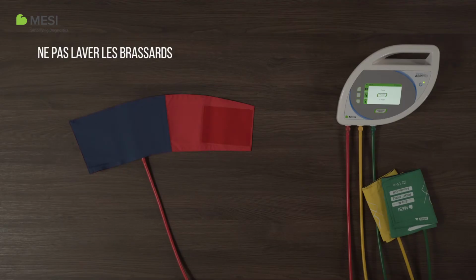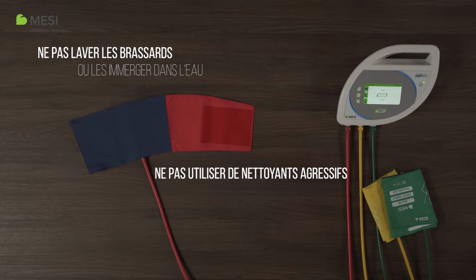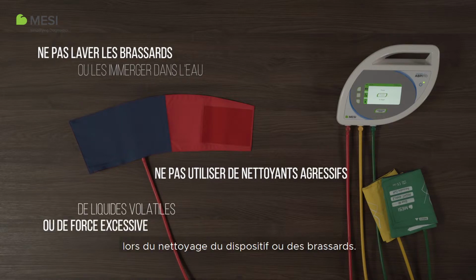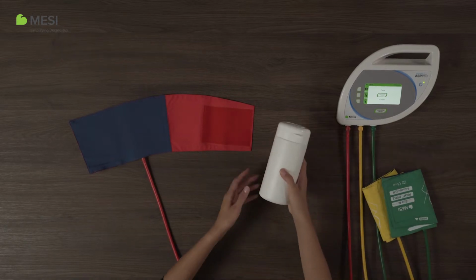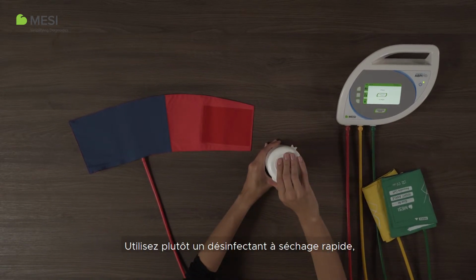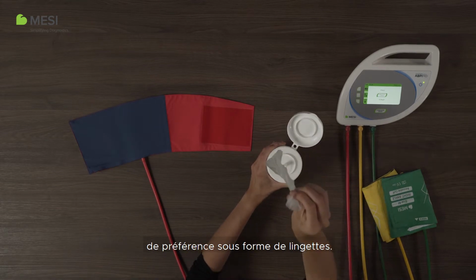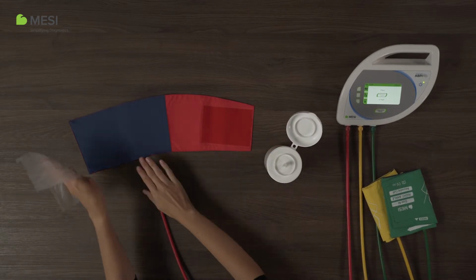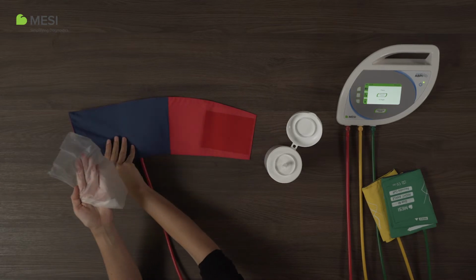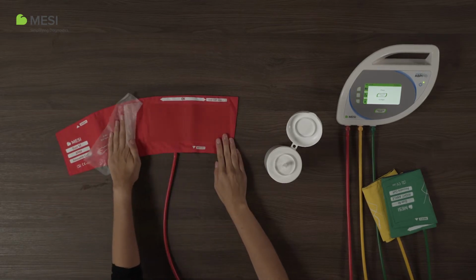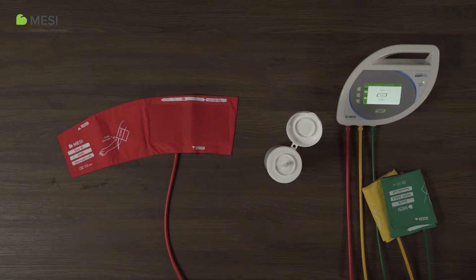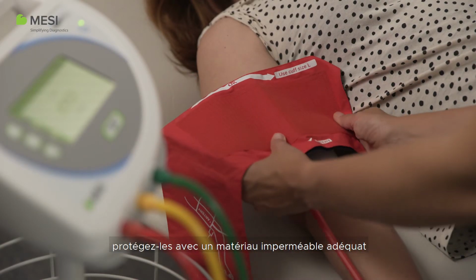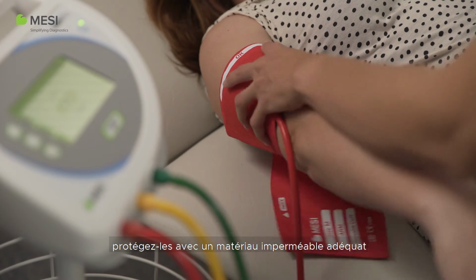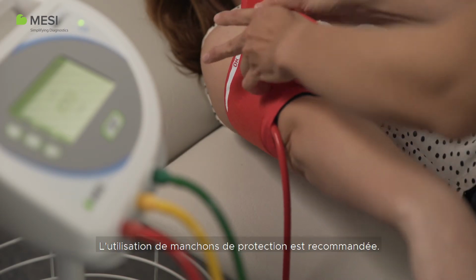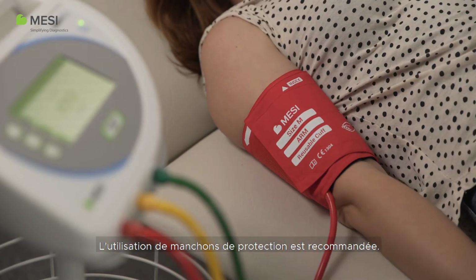Do not wash the cuffs or immerse them in water. Do not use aggressive cleaning agents, volatile liquids, or excessive force when cleaning the device or the cuffs. Instead, use a quick-drying disinfectant, preferably in wipe form. In case of open wounds, protect the wounds with adequate impermeable dressing prior to applying the cuffs. The use of protective sleeves is recommended.